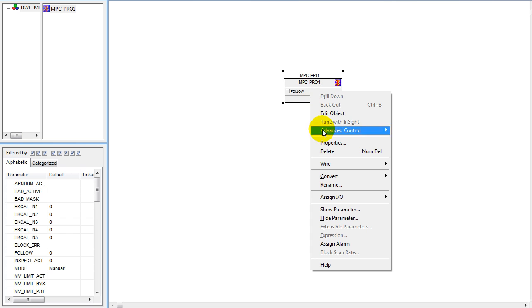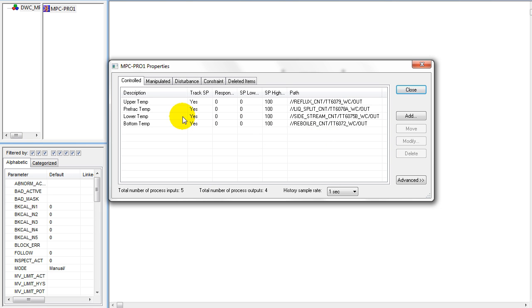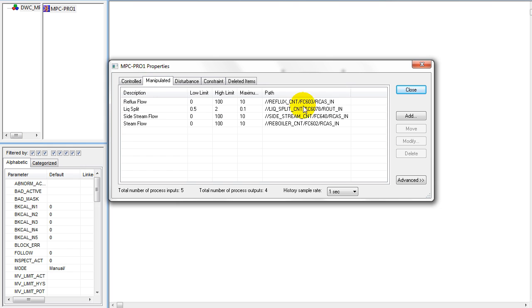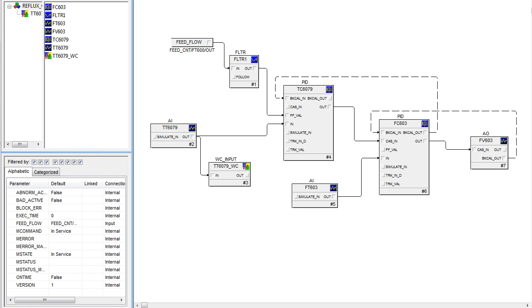Model predictive control is embedded within the control system. Here we're examining the setup of the control. Our control parameters are the four temperatures that indicate properties of the column. Our manipulated parameters are the flows — the flow setpoints of flow control loops associated with the column. By changing the mode, we can then adjust the flows of the independent flow loops.